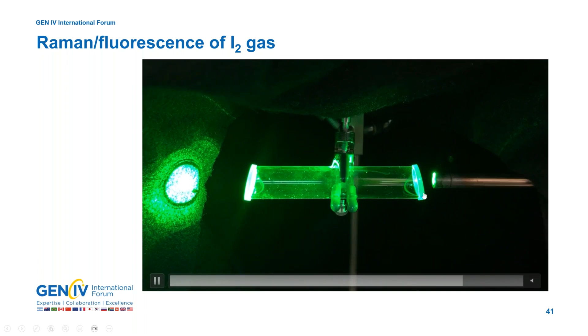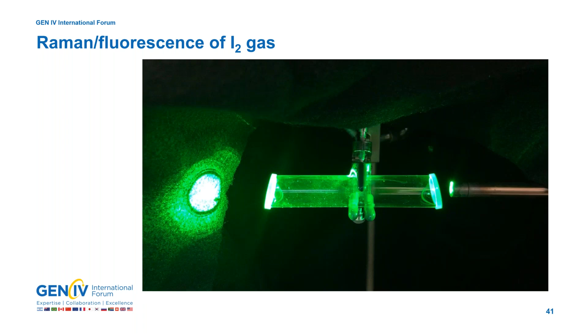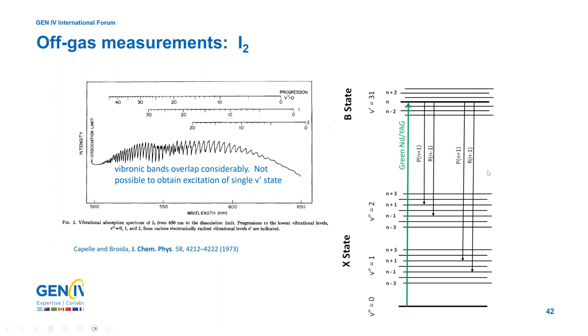What we intended to do is measure the Raman spectrum of this I2, but what we got in addition to the Raman measurement is also this very sensitive fluorescence band coming out. What that fluorescence is due to, this is a spectrum from the literature of iodine in the gas phase, the UV-Vis spectrum of it, showing a nice vibronic progression, a lot of vibronic bands on top of this absorption band. We're illuminating at 532 nanometers excitation right on top of a lot of vibronic progressions. And so we're shining light and getting into an excited vibronic state, and we get light emitting and nice fluorescence bands coming out into the visible spectrum.